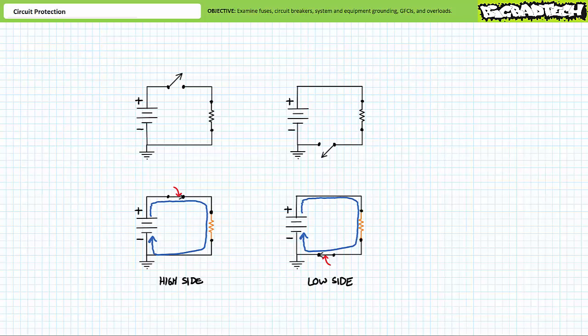Compare and contrast the behavior of these two systems when some errant conductive object accidentally makes contact with the electrical load and ground. Let's say this electrical load is some motor designed to cut a full-grown Doug Fir into a thousand toothpicks, obviously a device you want to keep an eye on when working in or around it. For obvious reasons, the switch needs to be open to ensure the device doesn't suddenly jump to life. In the high side switched arrangement, an accidental connection of the load to ground does not energize the load because the load is already at ground potential due to the system ground connection and open switch.